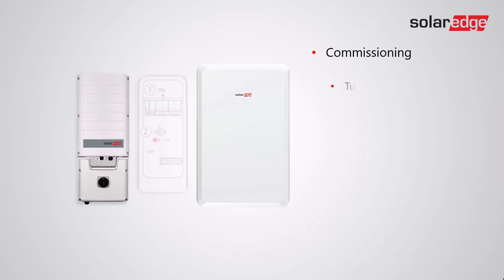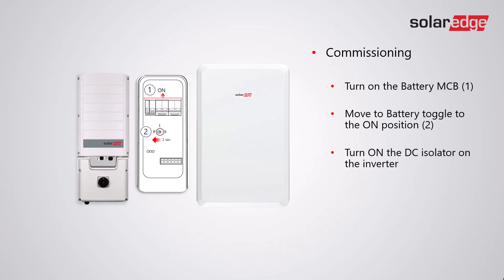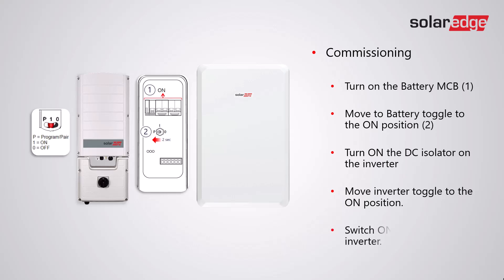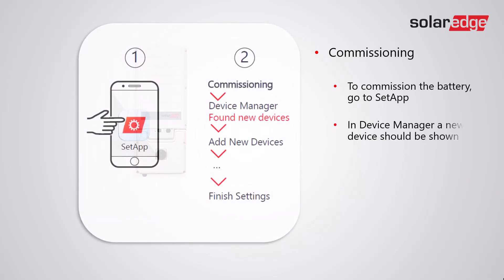For commissioning, turn on the battery MCB, move the battery toggle to the on position, turn on the DC isolator on the inverter, move the inverter toggle to the on position, then switch on the AC to the inverter. To commission the battery, go to SetApp. In Device Manager a new device should be shown — follow the guided prompts to set up the battery.